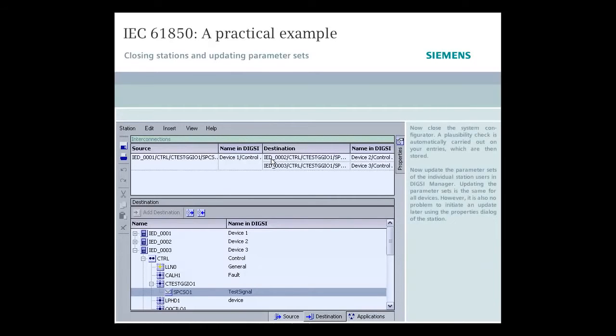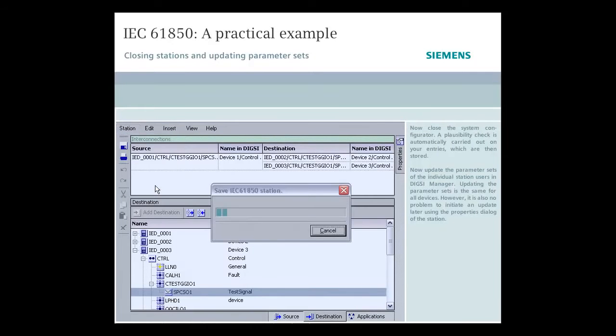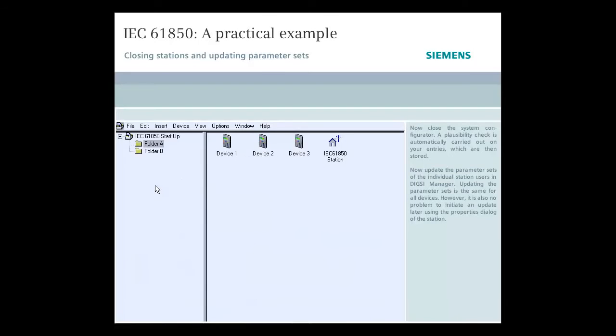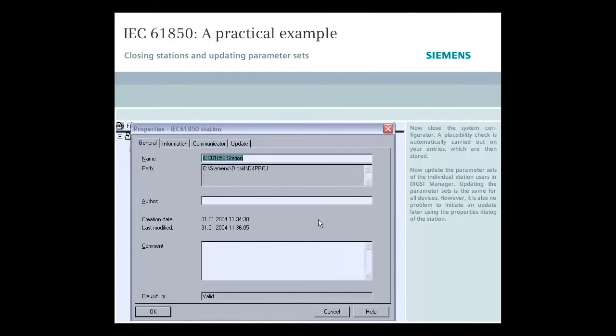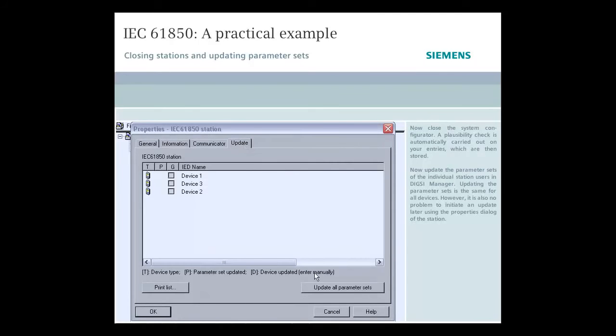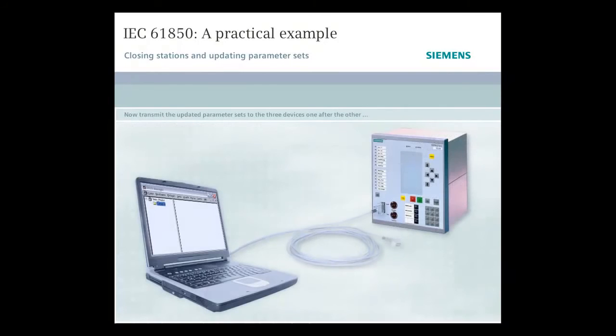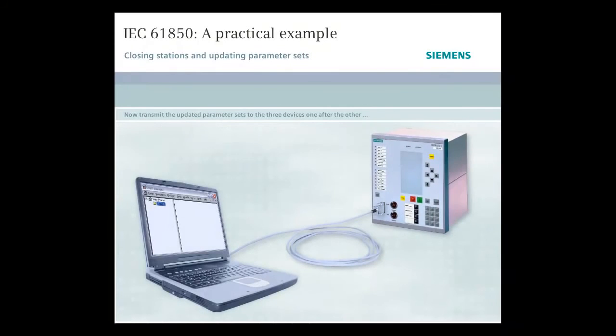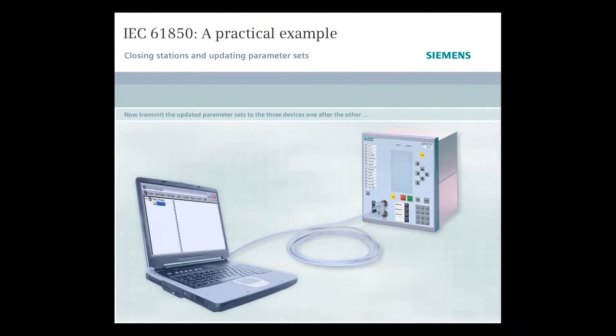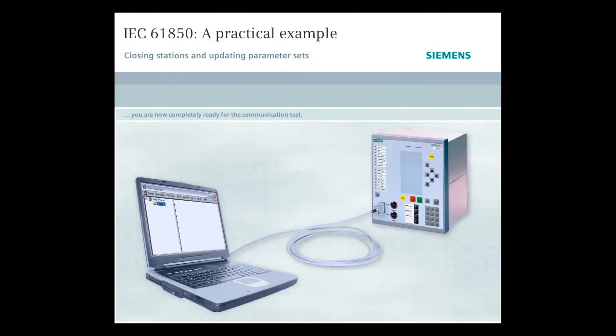Now close the system configurator. A plausibility check is automatically carried out on your entries, which are then stored. Now update the parameter sets of the individual station users in DIGSI Manager. Now transmit the updated parameter sets to the three devices one after the other, and you are now completely ready for the communication test.